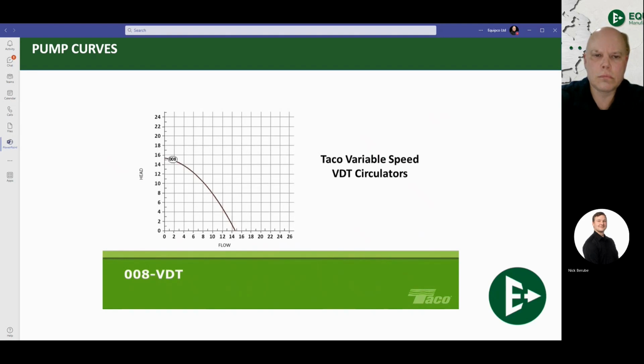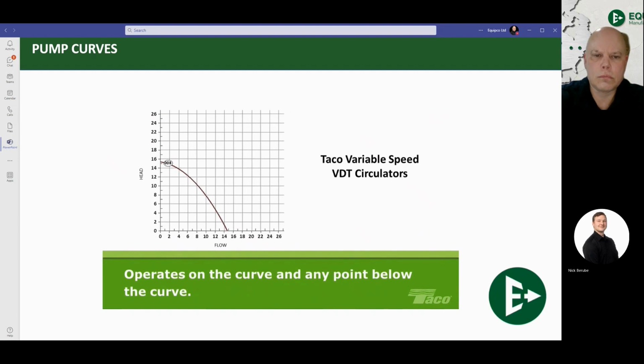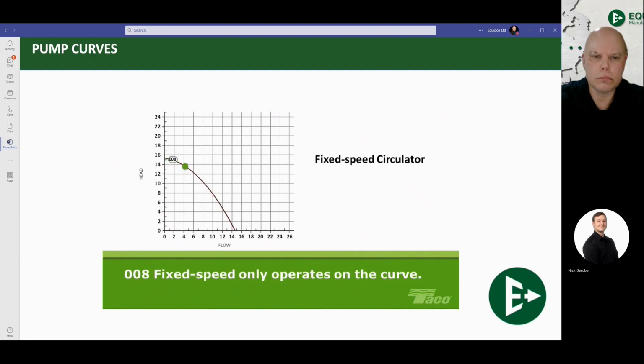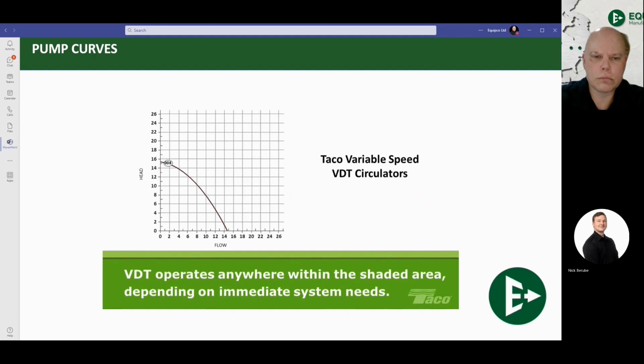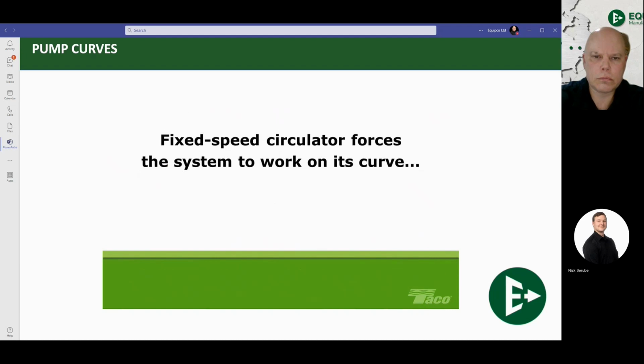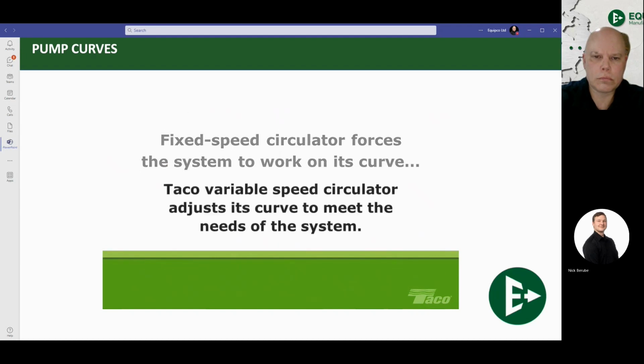It looks the same as the curve for any fixed-speed circulator, but you read it very differently. A Taco VDT circulator operates on its own curve, just like every other pump. But it also operates at any other point below the curve, depending on the needs of the system. In contrast, this 008 fixed-speed pump can operate only at points along its curve, not above or below it. The pump has no choice but to operate on its curve, and it doesn't matter what head and flow the system needs at any given moment. But the VDT variable speed pump can and does operate anywhere within the shaded area, depending on the specific immediate flow and pressure needs of the system. In other words, a fixed-speed circulator forces the system to work on its curve. A Taco variable speed circulator adjusts its curve to meet the needs of the system.